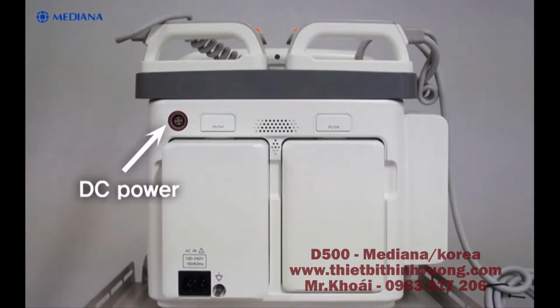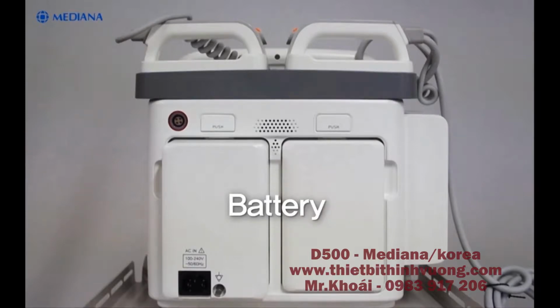For the DC power, the external DC power source can be used when the D500 is used for emergency conditions in a moving car. You can connect an external DC-DC adapter to the D500 rear panel connector identified with the DC power symbol. And then please verify that the DC power input icon appears on the screen. The battery charging status LED and AC-DC in LED on the D500's front panel are lit. Finally, for the battery use, the D500 has a rechargeable battery that can be used to power the D500 when the AC power source or external DC-DC adapter is not available. The battery status icon appears on the screen when the D500 is on battery.